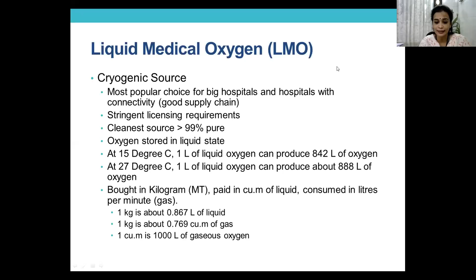1 kg is about 0.867 liters of liquid oxygen, which is about 0.769 cubic meters of gas. And 1 cubic meter is about 1,000 liters of gaseous oxygen. So this is something you'll need to remember. Now, vessel to vessel, there are variations with the diameter, the height. So how much each vessel can store is dependent on the supplier. And there's something known as a conversion chart that is available with each LMO and the supplier, which you will need to go through.